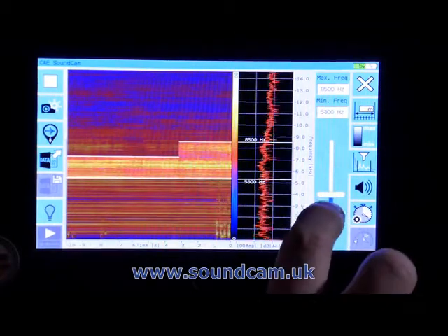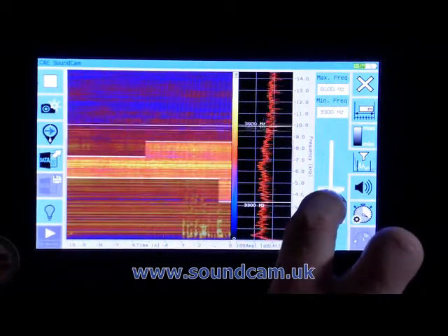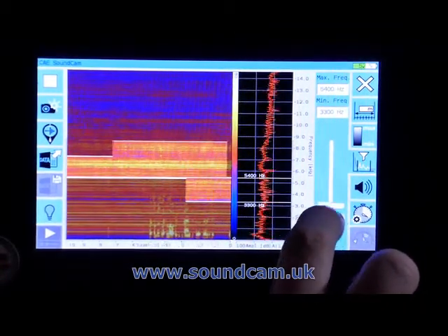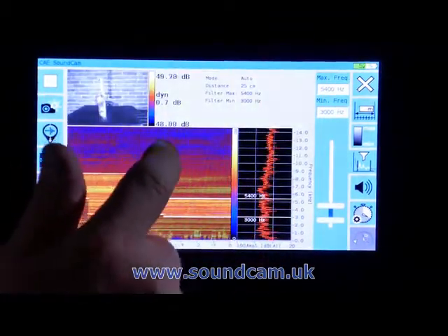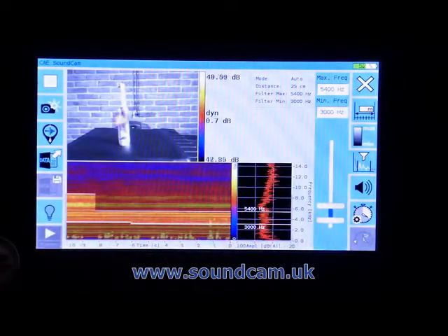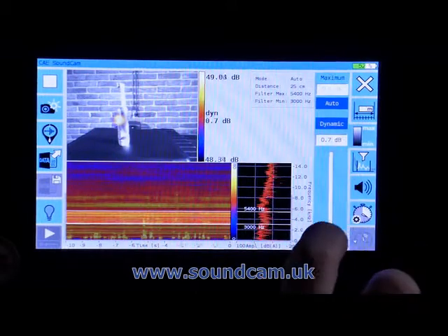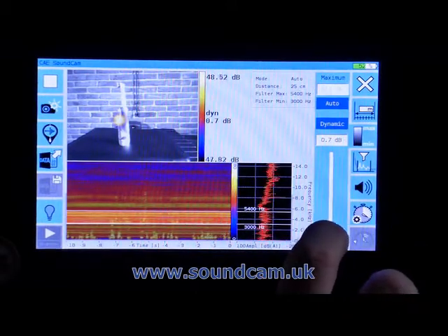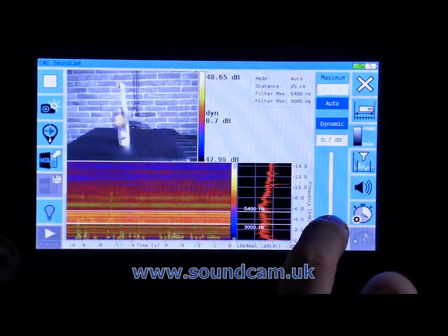Right, so I'm going to select a lower frequency band just to vary a bit where there's quite a lot happening, quite down here somewhere. You see there's still quite a lot of activity over a broad range. And now we're starting to see there is something going on at the top, but mostly it's coming from down below where the motor gearbox sort of area is.